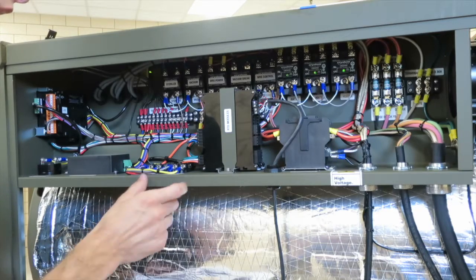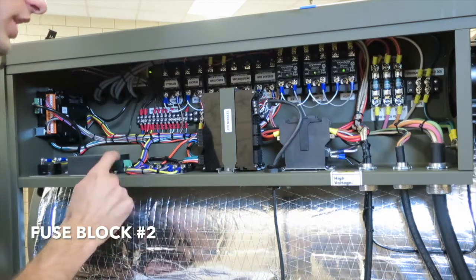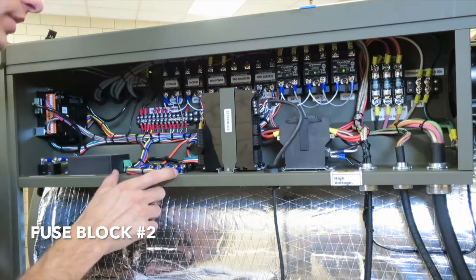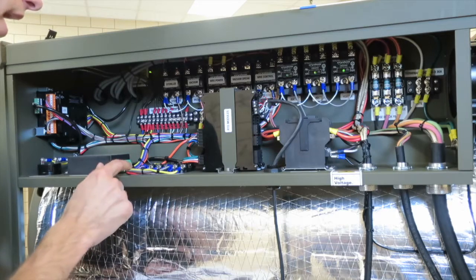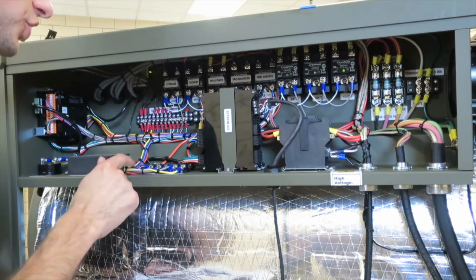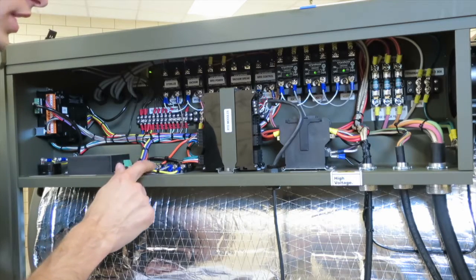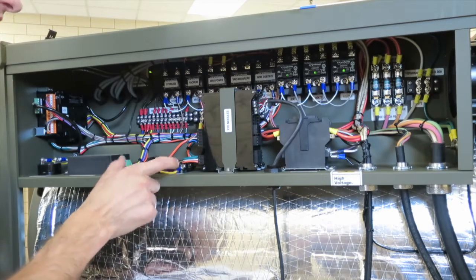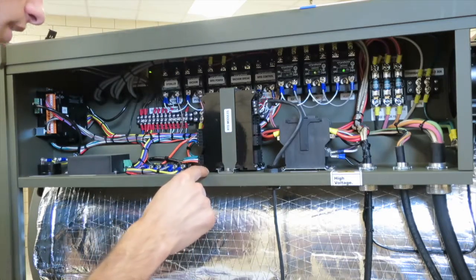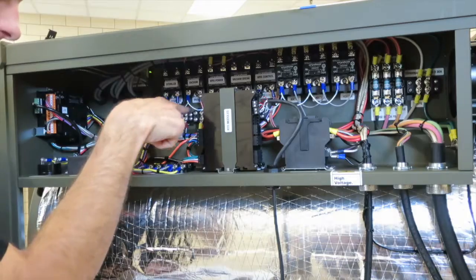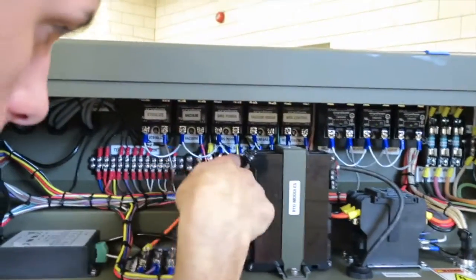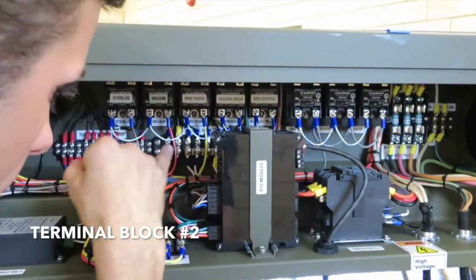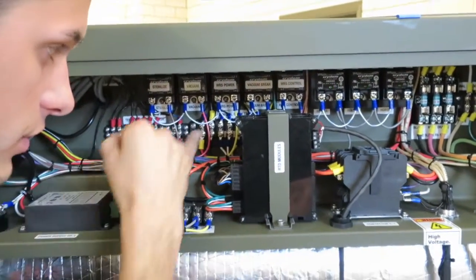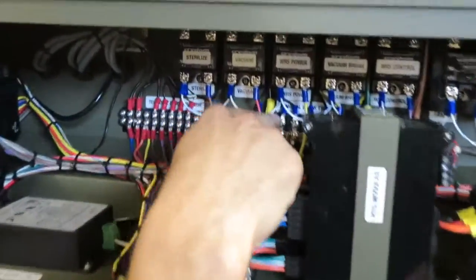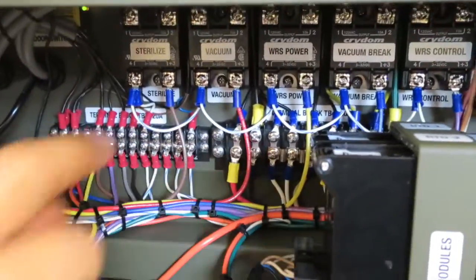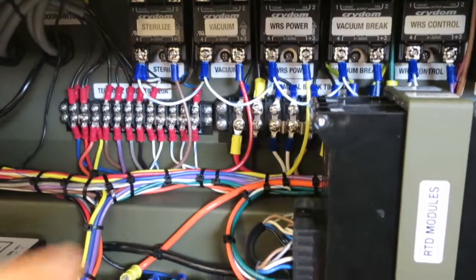Right here we have fuse block number 2. These all use the same fuse. It's a replacement part in your manual. And these first 2 right here are 120 volts and the rest are 24 volts. So that's fuse block number 2. Right here in the back, it's kind of hard to see, we have terminal block number 2. You'll see we have a lot of 120 volts. Across the bottom we have some of the neutrals, some of the grounds. But that is fuse block number 2 right there. Sorry, that's terminal block number 2.